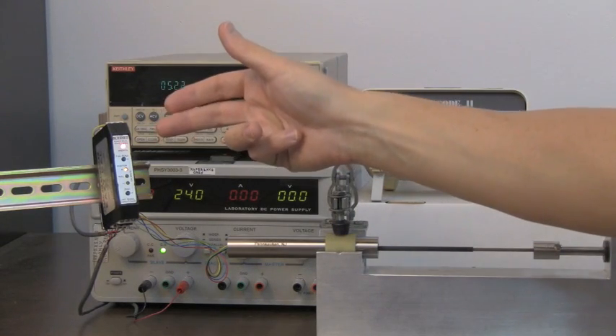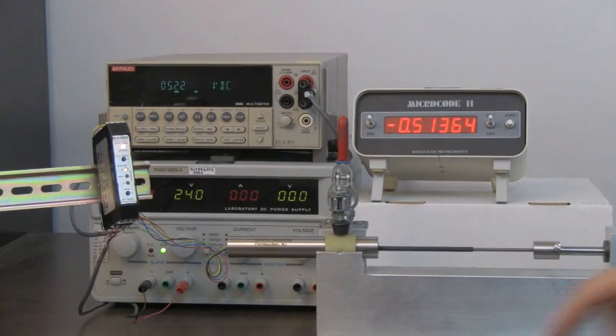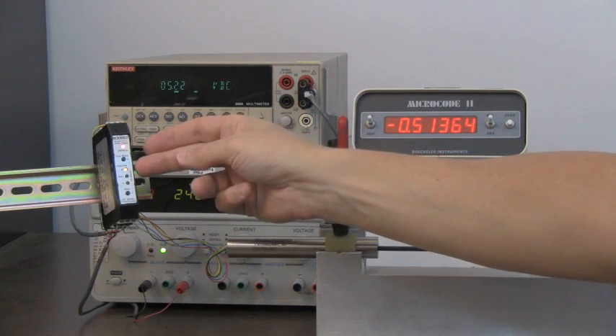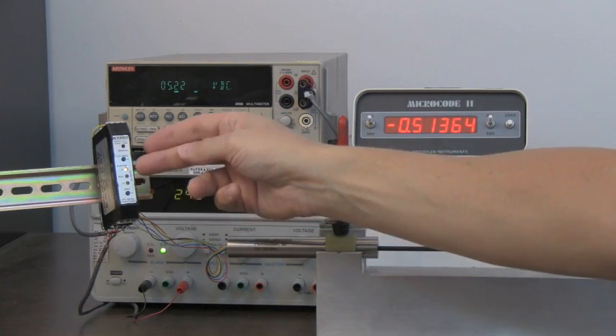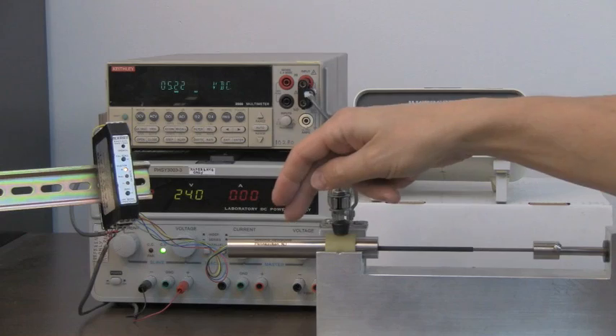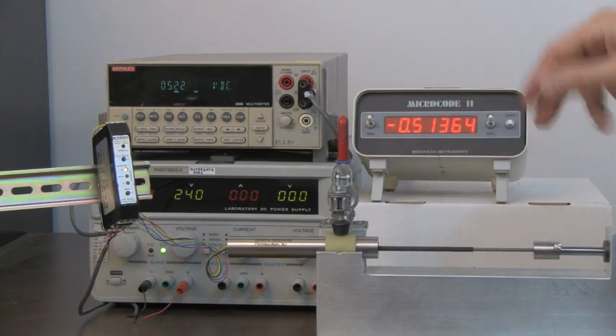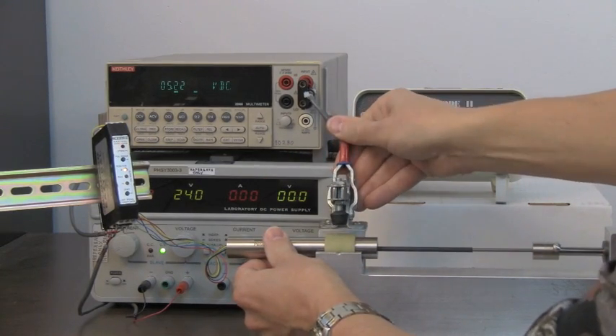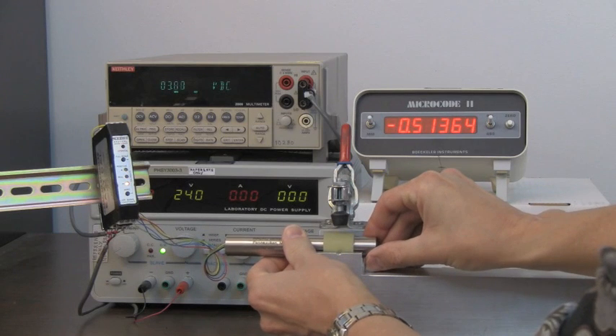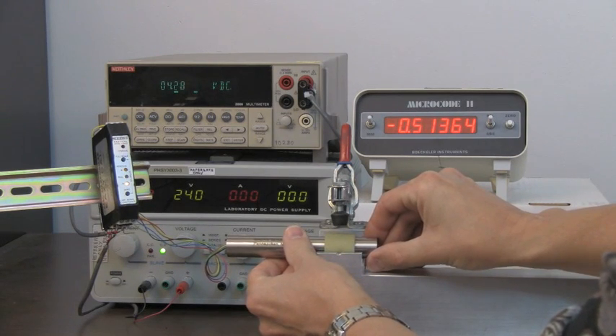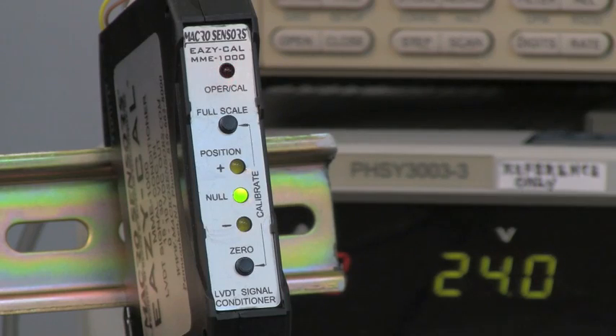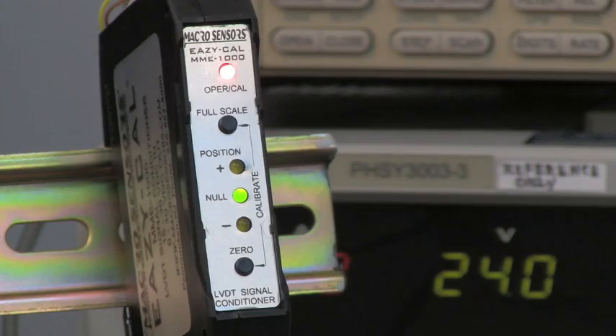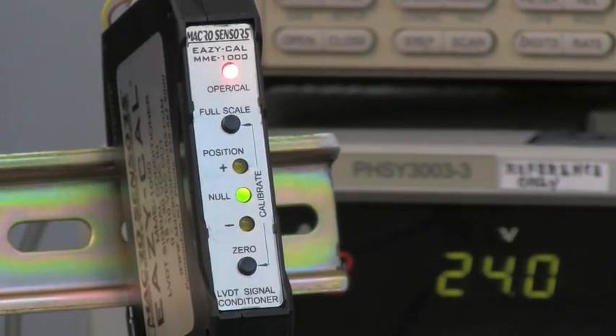Now that we have entered calibration mode, you will notice that the plus and minus LED lamps above and below the null LED indicator lamp will flash on and off as the LVDT coil is passed up and down the core. These lamps provide a visual position indication of the coil relative to the core. When perfectly centered, the null LED indicator lamp will be steadily illuminated, meaning that the LVDT is at the center of its total stroke, or at null.